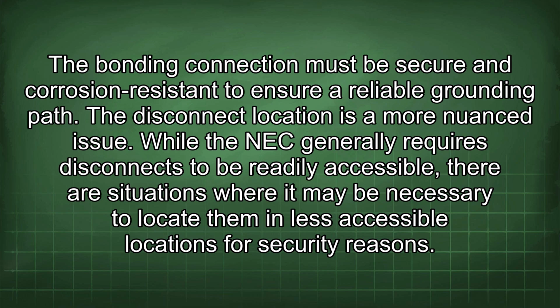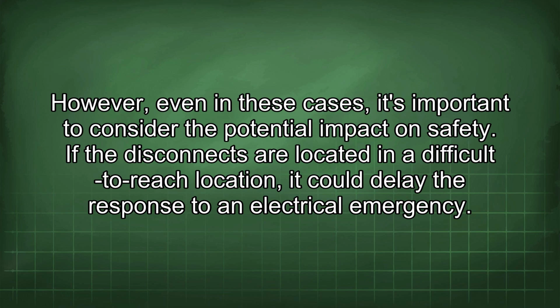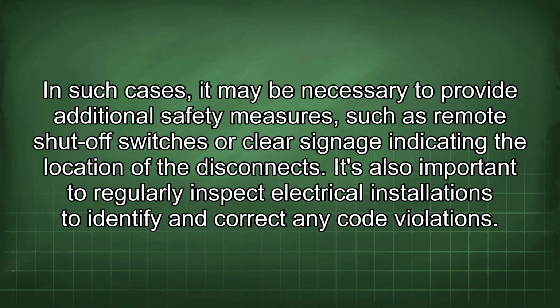The disconnect location is a more nuanced issue. While the NEC generally requires disconnects to be readily accessible, there are situations where it may be necessary to locate them in less accessible locations for security reasons. However, even in these cases, it's important to consider the potential impact on safety. If the disconnects are located in a difficult-to-reach location, it could delay the response to an electrical emergency. In such cases, it may be necessary to provide additional safety measures such as remote shut-off switches or clear signage indicating the location of the disconnects.